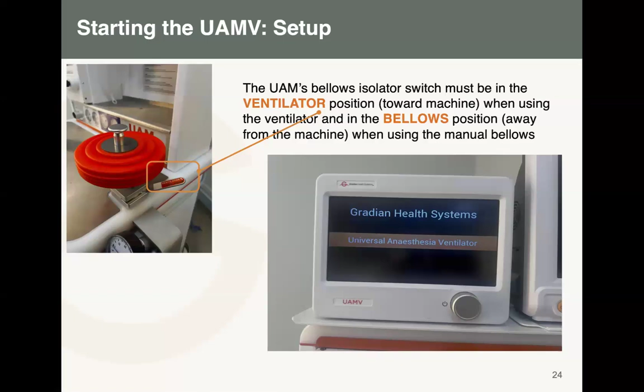For those who have experienced the machine, they will agree with me that if you start the vent and the isolator switch is on the bag side, the vent will put air in the bag, so there will be movement in the bag, and the machine will be alarming. And of course, we understand when the machine is panicking, everyone in theater panics. So to avoid those alarms and unnecessary noise, we always emphasize: if you are putting someone on the machine, change the bag switch first, then go and start the machine. When you're finishing your case, change the machine and come down and change the bag. Next, Mark.